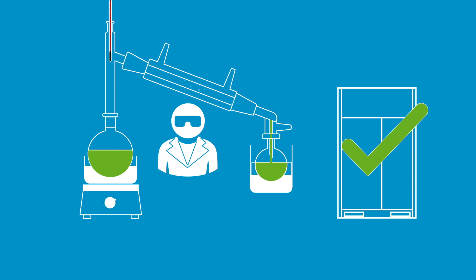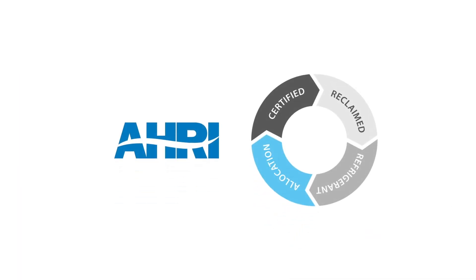Refrigerant recovered from a site can only be resold, passed on or exchanged if it meets the AHRI 700 standard. Using certified refrigerant is vital for the performance, efficiency and long life of the system and to ensure the warranty remains valid.